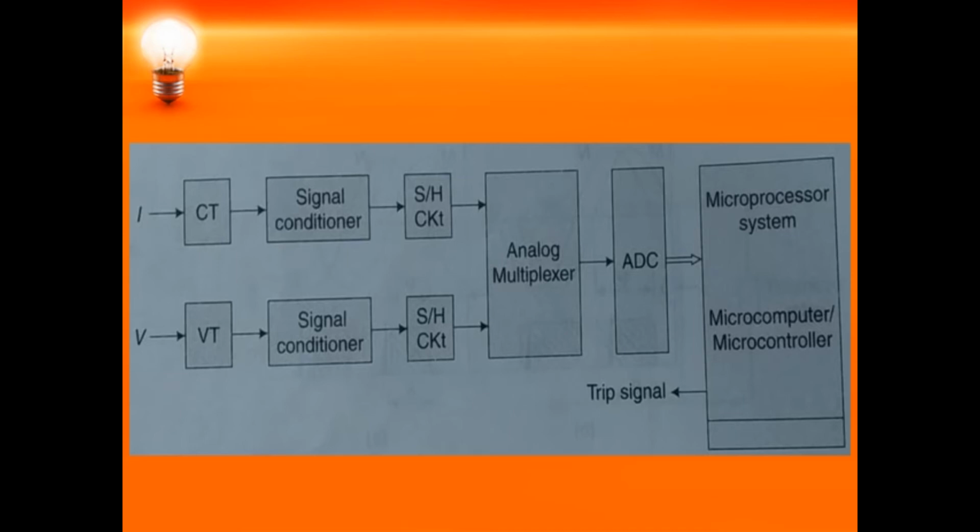It can be easily interfaced to a computer or a laptop communication system. The burden on these numerical relays is very low compared to mechanical relays, and they are very sensitive also. The speed of operation is very fast, and we can easily reset the numerical type relays. So these are the advantages of the numerical type relays compared to electromechanical type relays. Thank you.